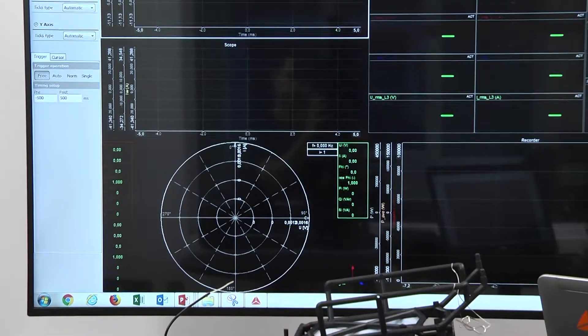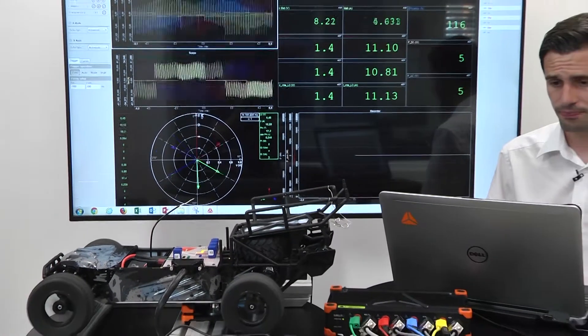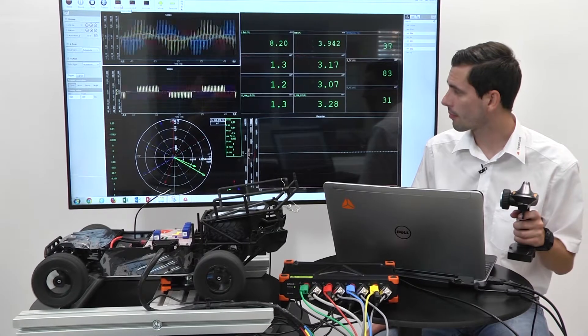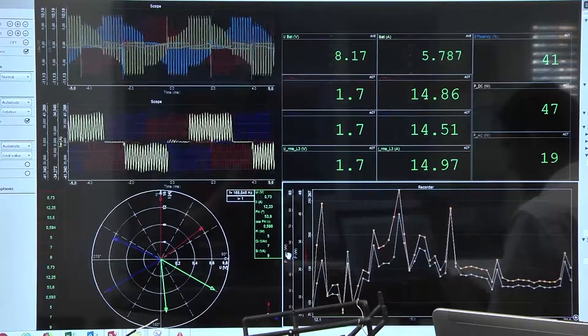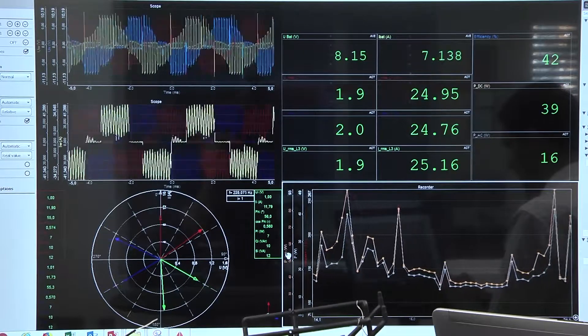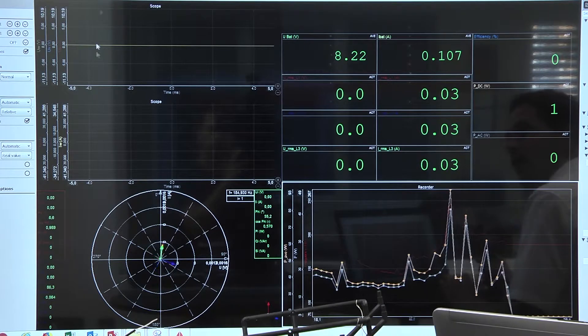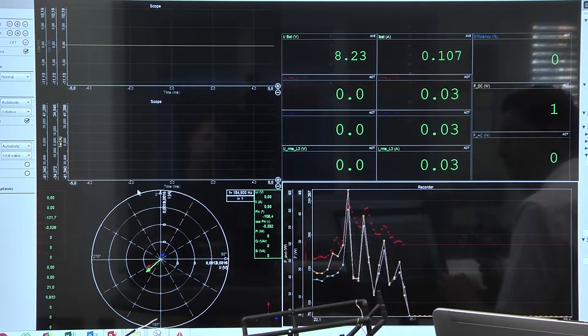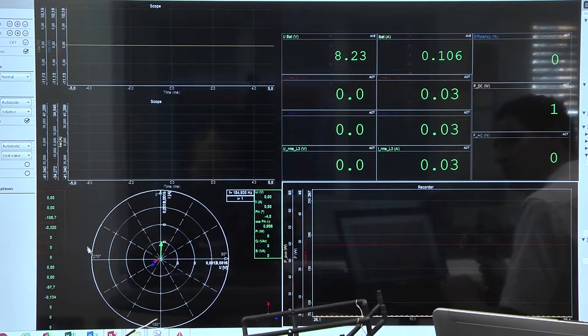In measure, as soon as I start the vehicle, we will see our readings. On the top left, we will see the scope for the voltage and the current. In the vector scope, we will see the three-phase system of voltage and current together with the phase angle.